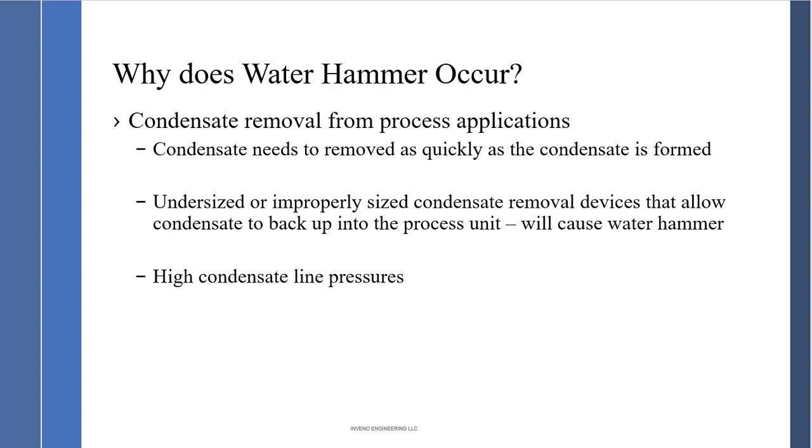Undersized or improperly sized condensate removal devices that allow condensate to back up into the process unit will cause water hammer. Sizing a steam trap is as critical as sizing a control valve in the system. So take the time and the effort to size the steam trap correctly. Understand the dynamics of the system. A steam trap is an orifice. You need to know P1 and P2. The other thing is high condensate line pressures. And not knowing the condensate line pressure, or P2, on the outlet of the steam trap is critical. And the thing about condensate line pressures, they can vary depending on the dynamics of the system. So we have to know the highest condensate line pressures.